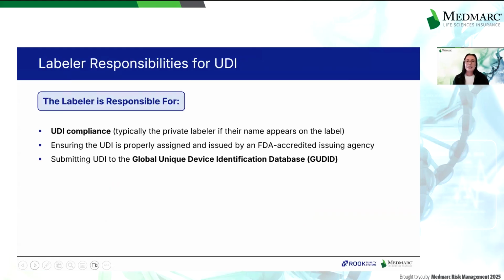Under FDA regulation, the labeler is defined as the person or entity that causes a label to be applied to a device or modified with the intent for commercial distribution. This includes private labelers, even if the original equipment manufacturer physically prints and applies the label. The private labeler is still considered the legal labeler if the device is marketed under their name. This designation is particularly relevant under the FDA's UDI regulations. The labeler's responsibilities include the UDI compliance. In most private label scenarios, this is the private labeler, as their name appears on the label.